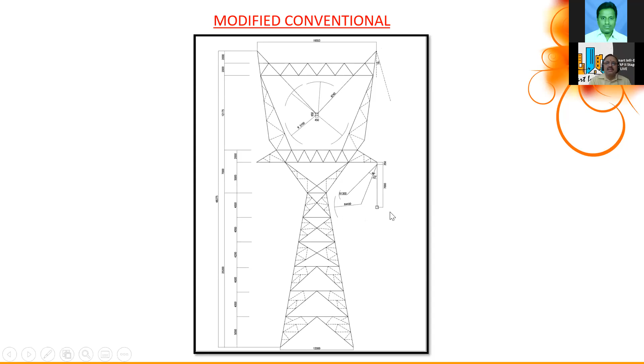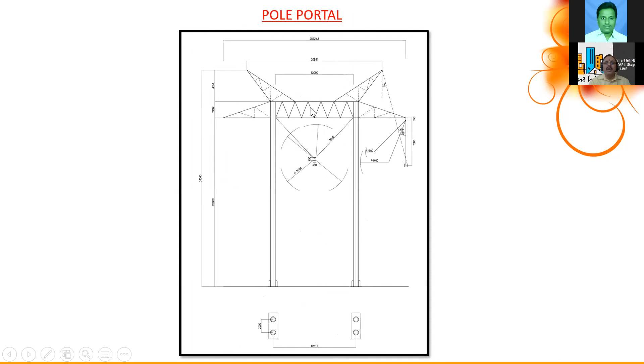We do the earthing of this shield wire. This is the pole portal, we used steel as a gantry. Here you can see the height is reduced because we reduced the span. These are the precast poles, spun concrete poles. We have designed with this and compared all three options.